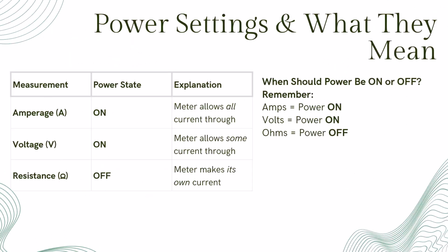Knowing whether to test with the power on or off is critical, not just for accuracy, but for your safety and the health of your meter. When your meter is set to amperage, A, it actually lets all the current pass through itself, so the power must be on. When measuring voltage, V, the meter lets some current flow through. It's also on. But when measuring resistance, ohms, the meter generates its own small current, so the power must be off. Remember the rule of thumb. Amps equals on, volts equals on, ohms equals off. Mixing that up can blow a fuse in your meter, or worse, cause serious damage.